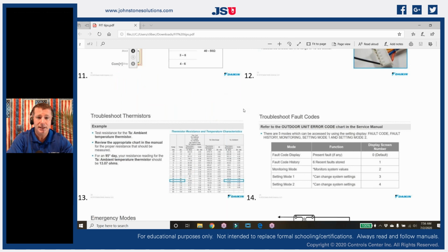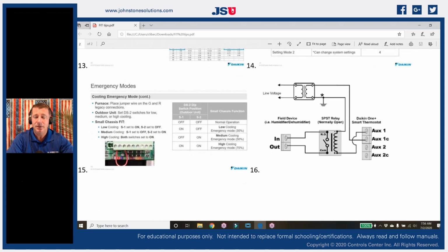So if I look at this chart and I say, hey, I've got 95 degrees outside, I can either unplug my sensor, and I should have around 13.07 k ohms of resistance, or if I check the DC voltage coming out of that, it's going to be about 1.42 volts DC. Super, super, super easy to read and understand these things. And when we think about it, it's all operating on this 5 volt DC signal. Well, what happens if we have a problem in our communicating network?